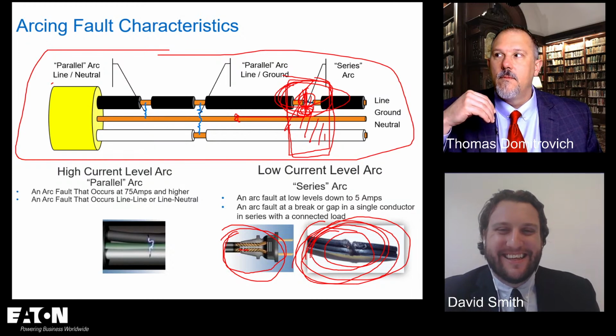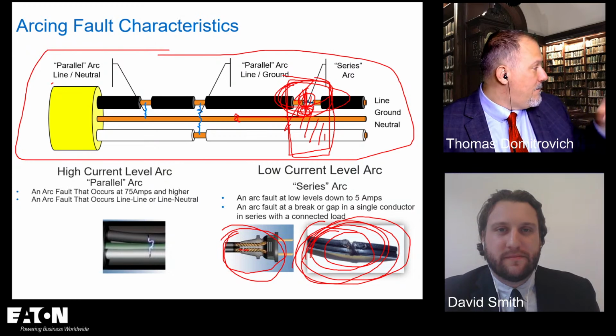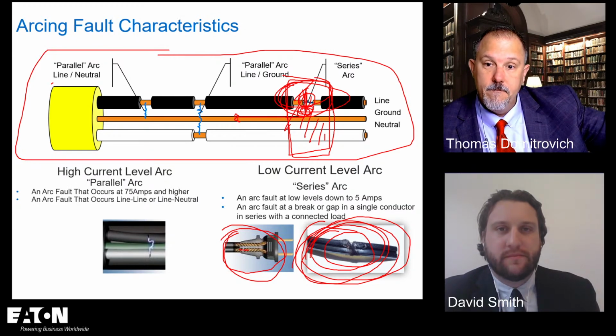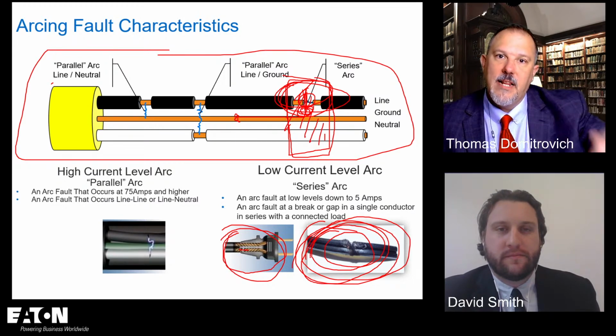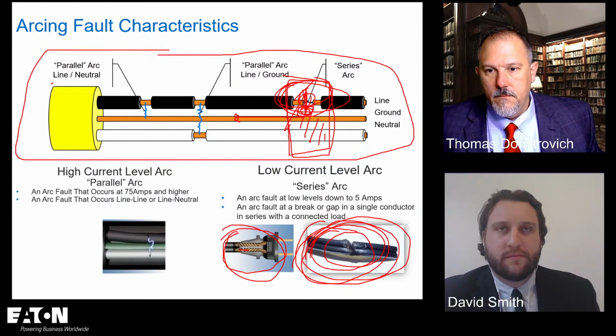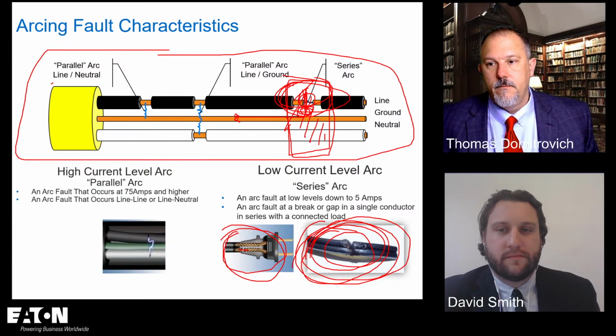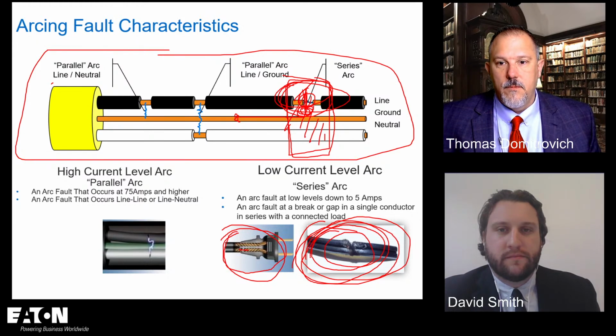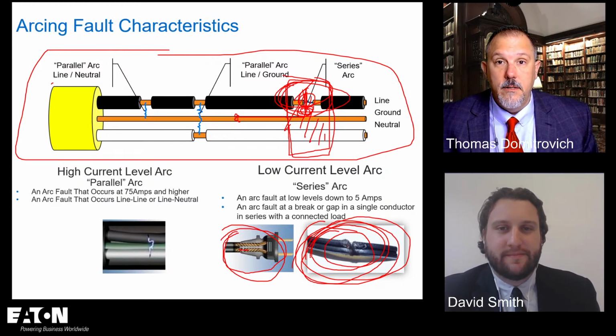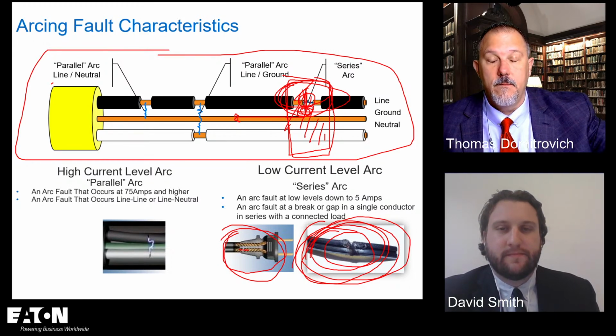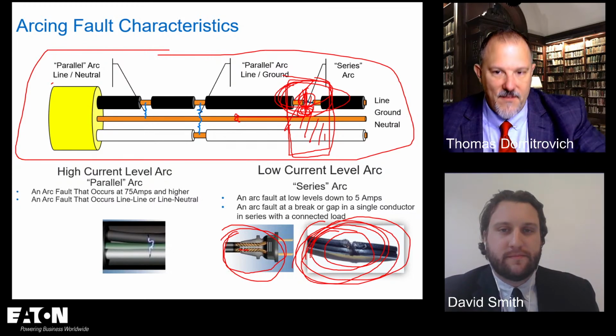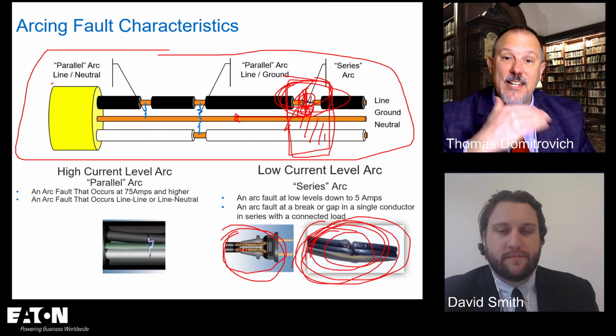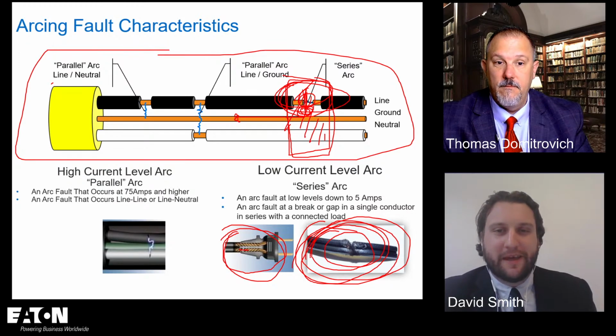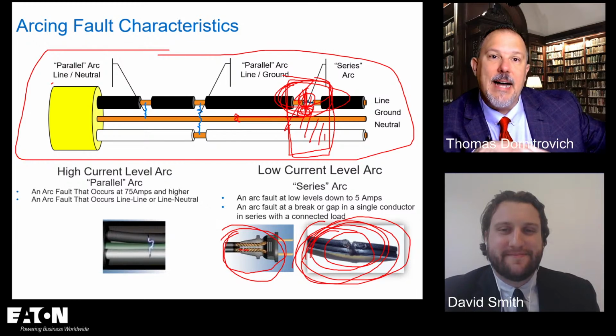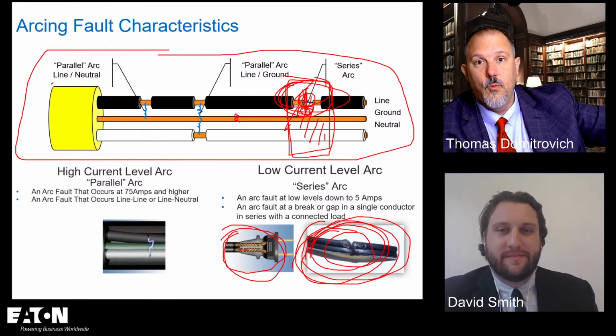Now, let's say that my computer cord has a problem, but I'm not detecting it because I'm not hitting that 5 amp threshold. Now let's say I plug in my vacuum sweeper and I turn it on. And now it trips. What am I going to blame? The vacuum sweeper, right? Because that's what I turned on when I was working, and that's what tripped the breaker. But the problem is not in the vacuum sweeper. The vacuum sweeper added enough load to the circuit to get you beyond that 5 amp threshold. It's the straw that broke the camel's back. It was what let the AFCI detect the problem in that smaller cord with the smaller load.